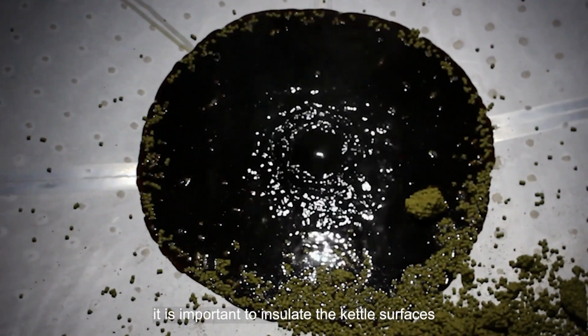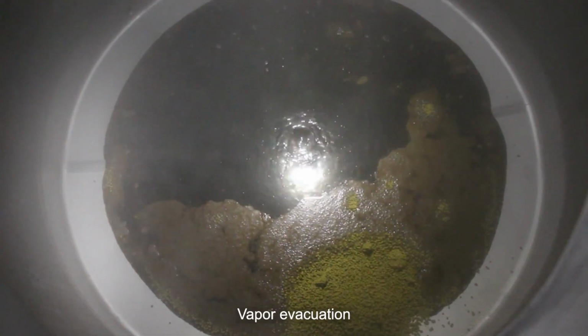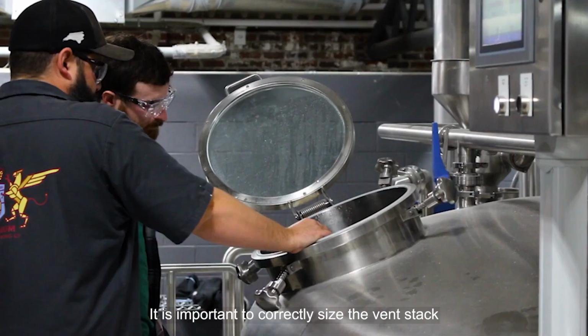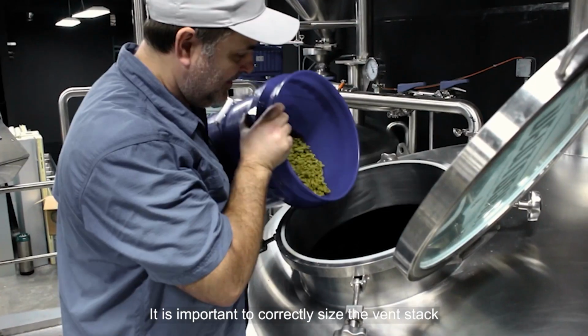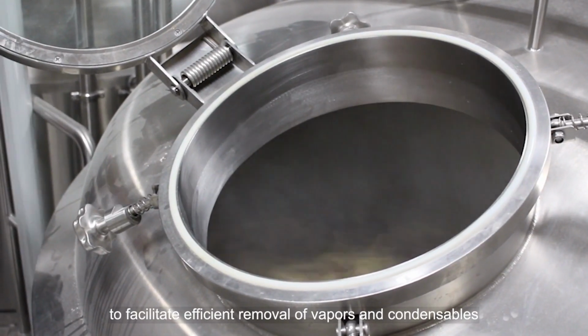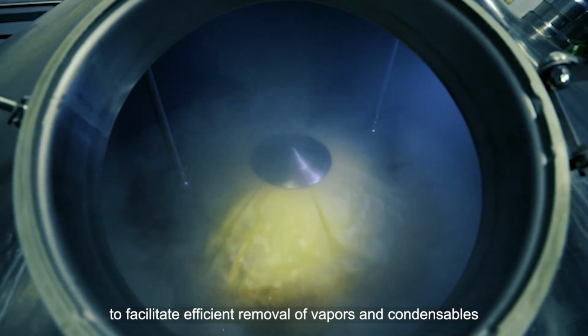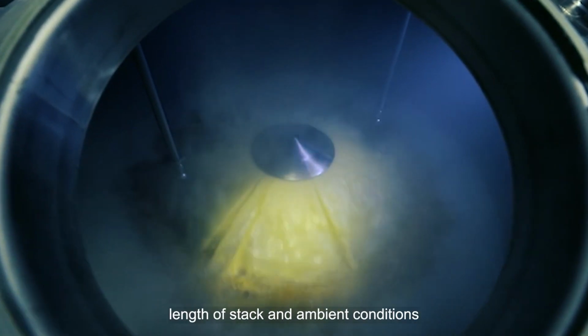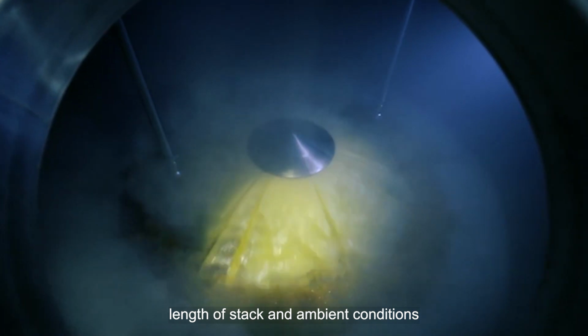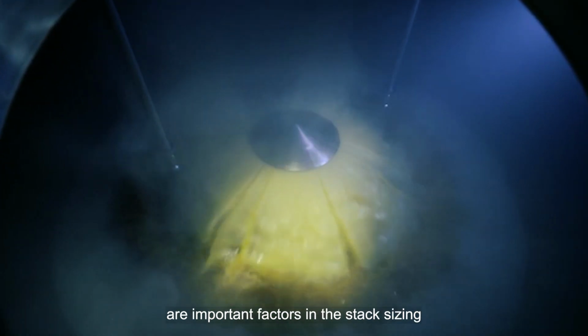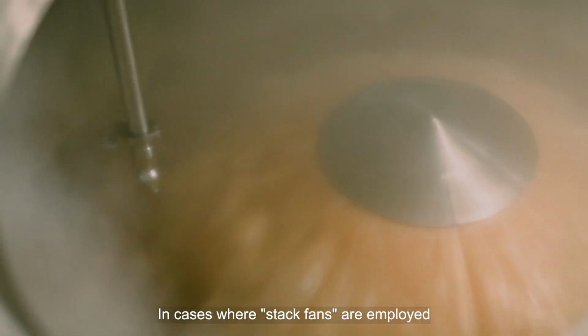It is important to insulate the kettle surfaces. Vapor evacuation. It is important to correctly size the vent stack to facilitate efficient removal of vapors and condensables. Evaporation rate, length of stack, and ambient conditions are important factors in the stack sizing. In cases where stack fans are employed, again sizing is key.